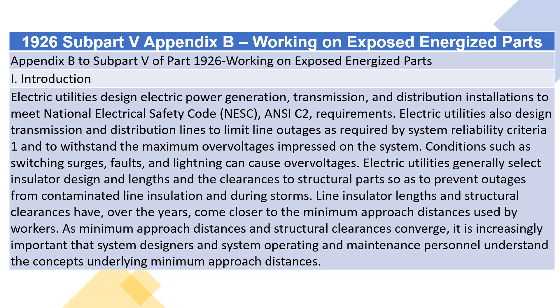Lines must withstand the maximum overvoltages impressed on the system. Conditions such as switching surges, faults, and lightning can cause overvoltages. Electric utilities generally select insulator design and lengths and the clearances to structural parts to prevent outages from contaminated line insulation and during storms. Over the years, line insulator lengths and structural clearances have come closer to the minimum approach distances used by workers. As minimum approach distances and structural clearances converge, it is increasingly important that system designers and operating and maintenance personnel understand the concepts underlying minimum approach distances.